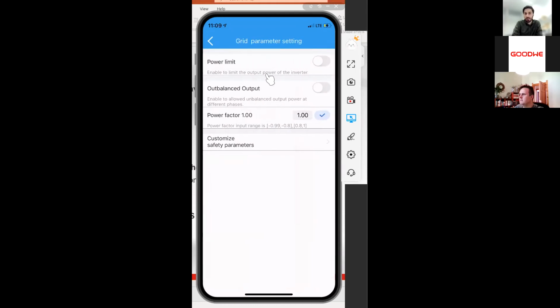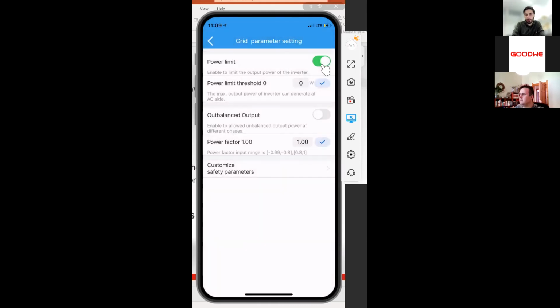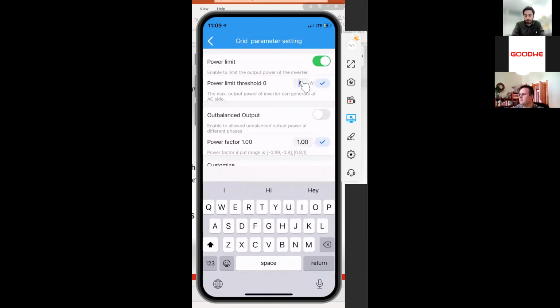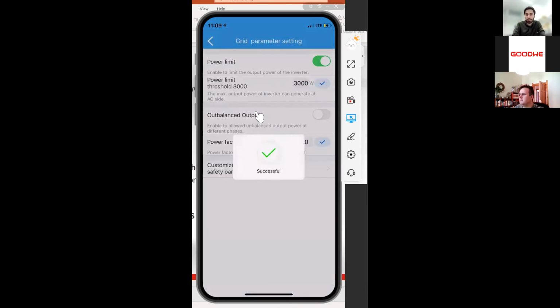So going back here, you need to check this in case you want to have some power limit on the, let's say we want to use all energy for ourselves and we're not allowed to export anything to the grid. Here you then set the threshold, so how much you want to be exported to the grid. In most cases, you don't want to export anything, but sometimes the grid provider says, okay, maximum 3 kilowatt. And then you add that as max, you press okay, and then it will be set.